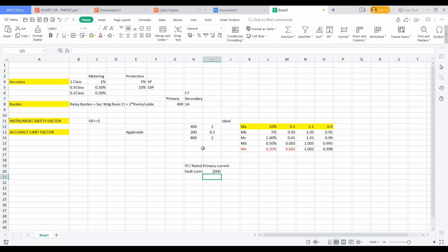Coming to protection, here the accuracy limit factor is the important one. Here is how we calculate the ALF. We have a 33 kV feeder and we create a fault here, and check the maximum fault. Suppose the maximum fault is 4000 amps.